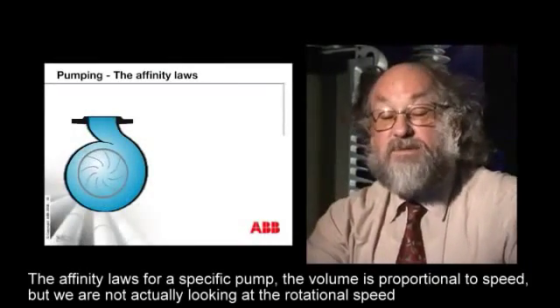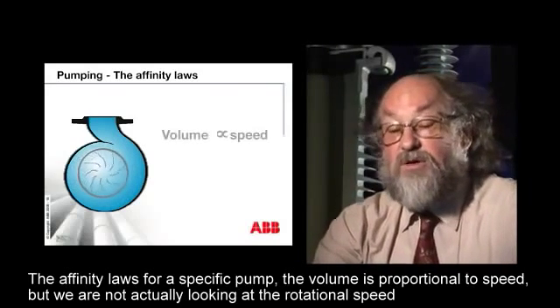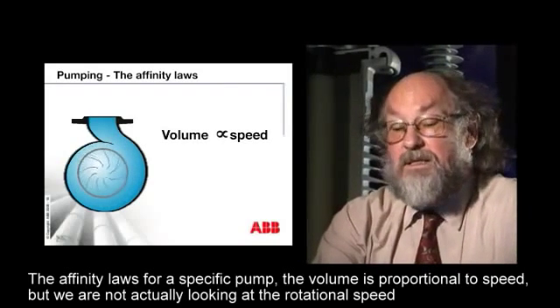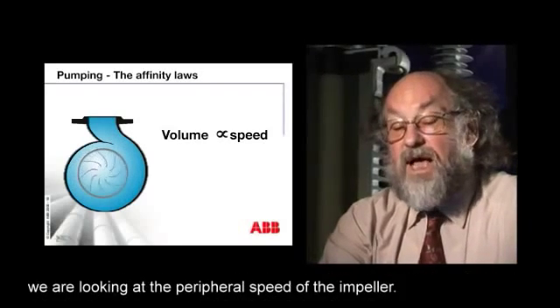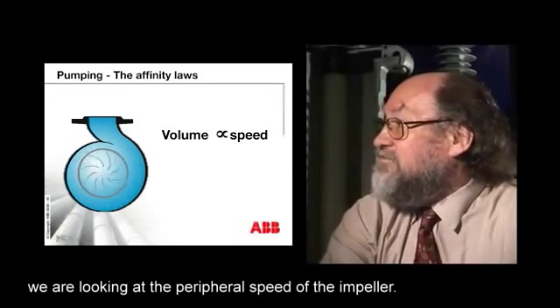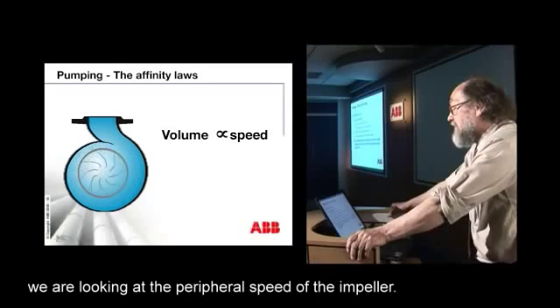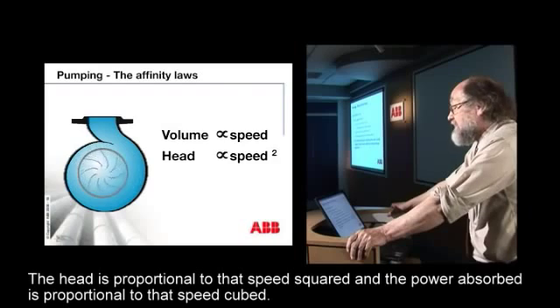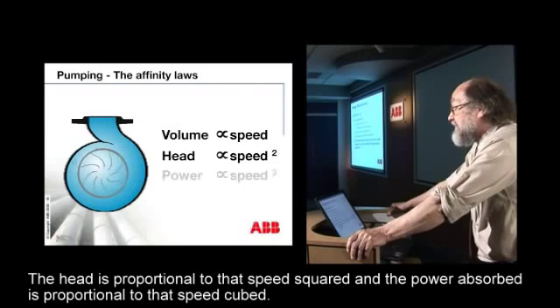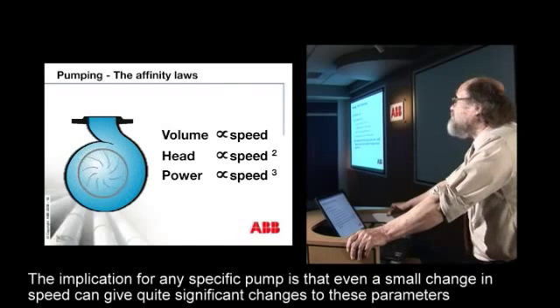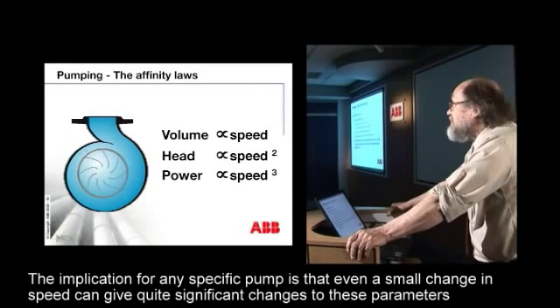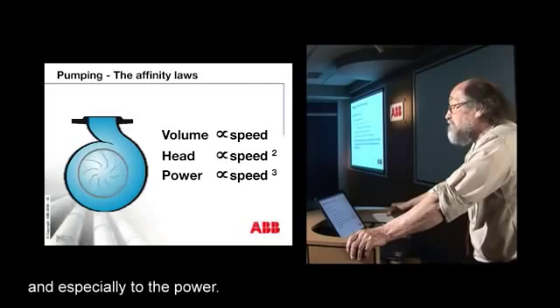The affinity laws for a specific pump state that volume is proportional to speed — and we're not looking at rotational speed, but the peripheral speed of the impeller. The head is proportional to that speed squared, and the power absorbed is proportional to that speed cubed. The implication is that even a small change in speed can give quite significant changes to these parameters, and especially to the power.